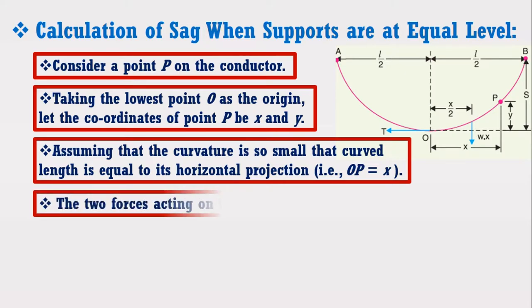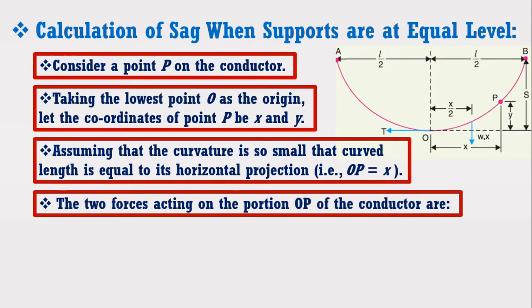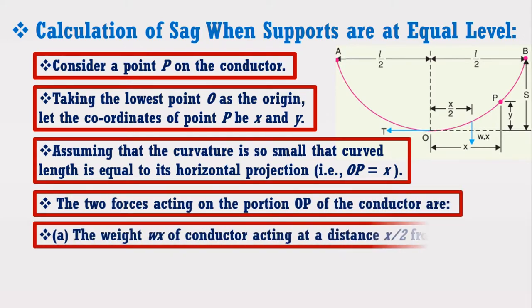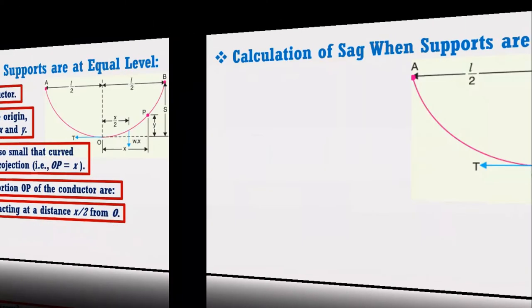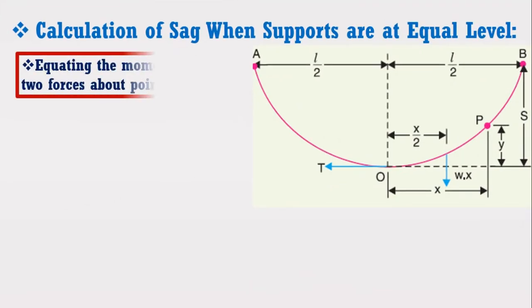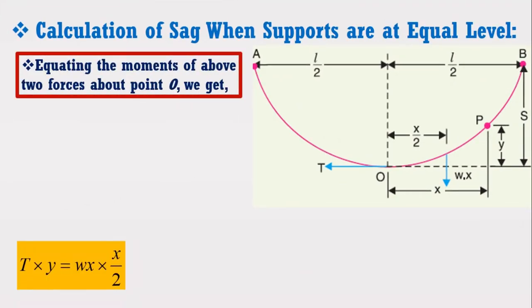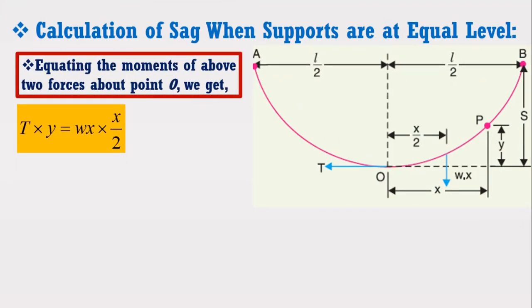The two forces acting on the portion OP of the conductor are: A — the weight WX of the conductor acting at a distance X upon 2 from O, and B — the tension T acting at O. Equating the moments of these two forces about point O, we get an expression from which the formula for Y is derived.